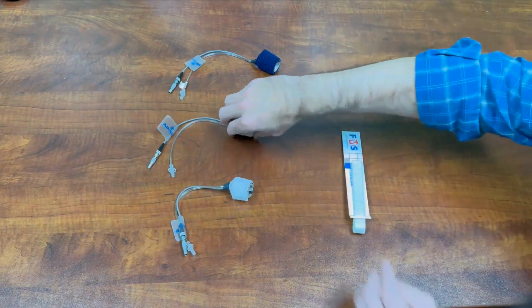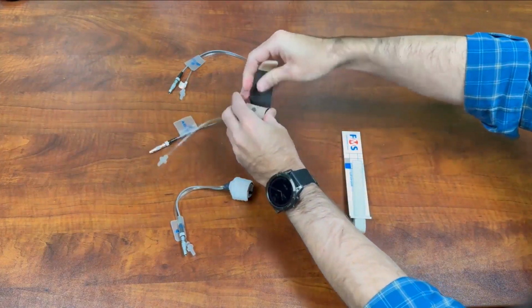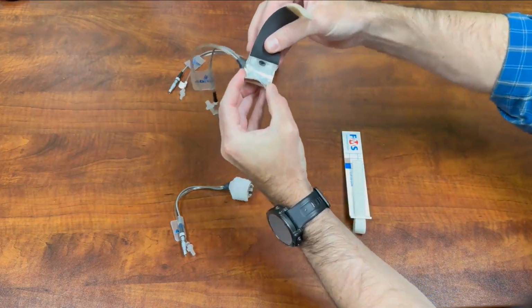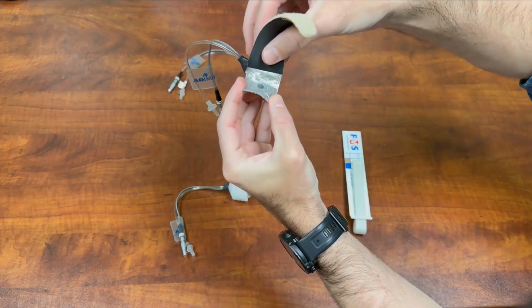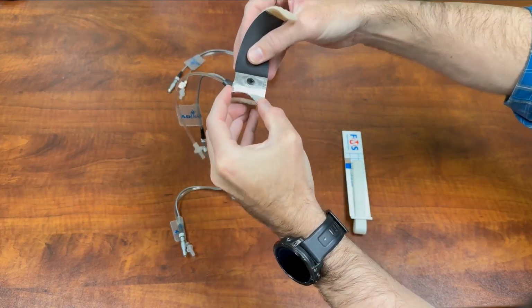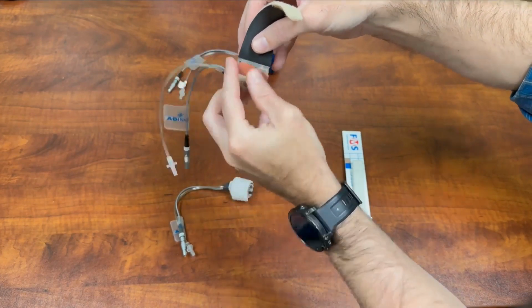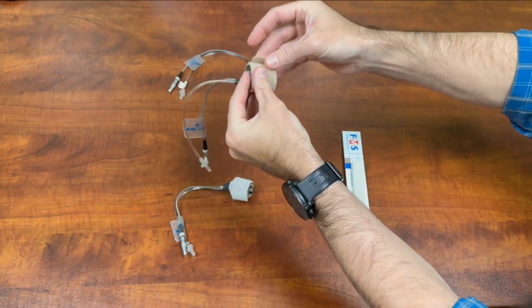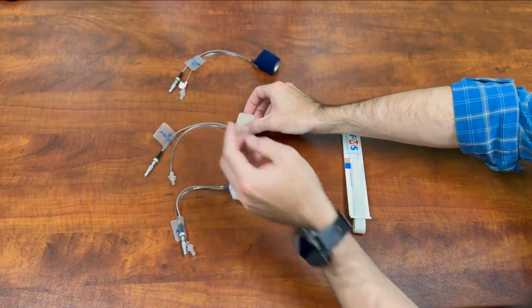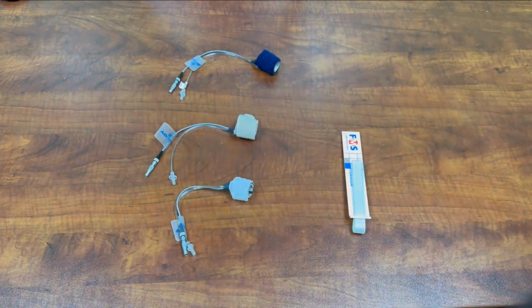The NOVA finger cuff consists of an inflatable bladder and plethysmograph, which incorporates an LED light source and detector. The light is absorbed by the blood, and the pulsation of arterial diameter during a heartbeat causes a pulsation in the light detector signal. When a subject has cold fingers, the blood pressure measurement can be difficult. Therefore, perform a measurement at room temperature, ask the subject to wear comfortable clothes, and it is important to keep the hand, finger, arm, and even neck warm. Wearing gloves or holding a heating pad prior to putting the finger cuffs on is a common technique we see in the field.